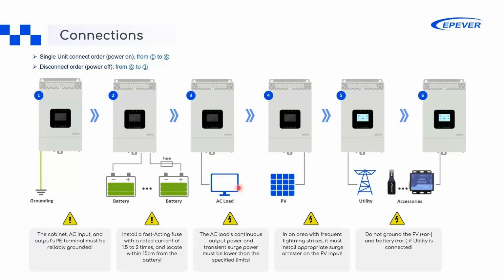Then we need to connect the AC load, ensuring the continuous output power and the transient surge power of the load are below the specified limits to prevent any damage to the inverter. It's also recommended to have protections on the load side to protect both the loads and the inverter from anomalies.